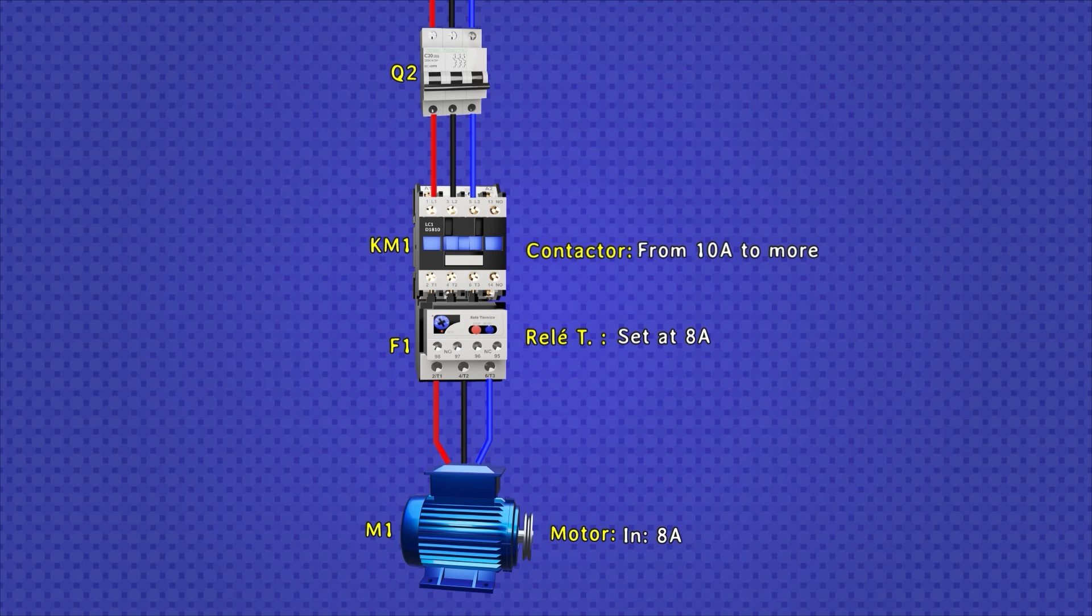This is why the thermal relay must be adjusted to the same working current intensity of the motor. As for the contactor, it is recommended that it can withstand a current intensity of at least the maximum current intensity of the thermal relay. That is, for this case, as the thermal relay can be adjusted from 7 amps to 10 amps, then the contactor must support at least those 10 amps. If it supports more, it is better.